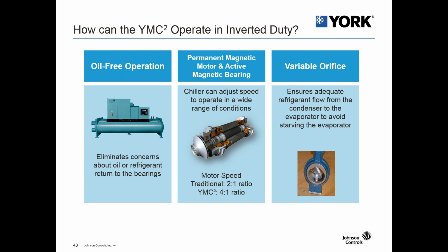And we also have a variable orifice. This is the main component that connects the whole system together. The expansion valve between the evaporator and the condenser, by having a variable orifice, allows adequate refrigerant flow from the condenser to the evaporator to control that differential between the two circuits to ensure that the evaporator doesn't starve and the condenser stacks up and the chiller shuts down on low evap pressure.